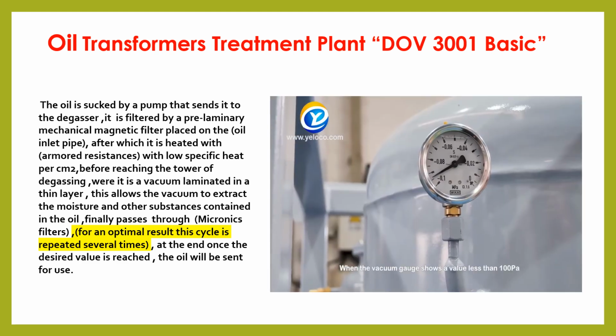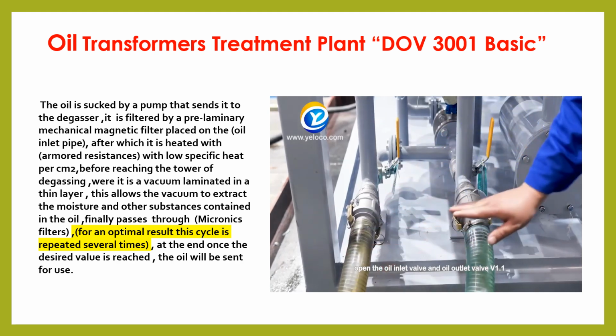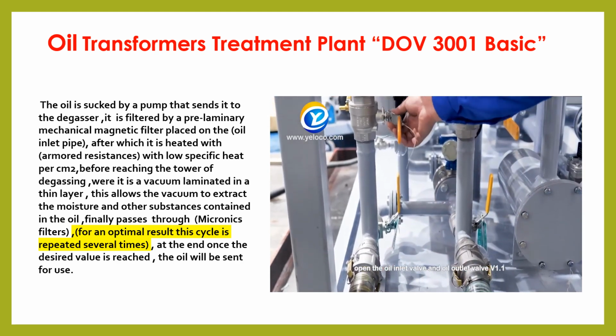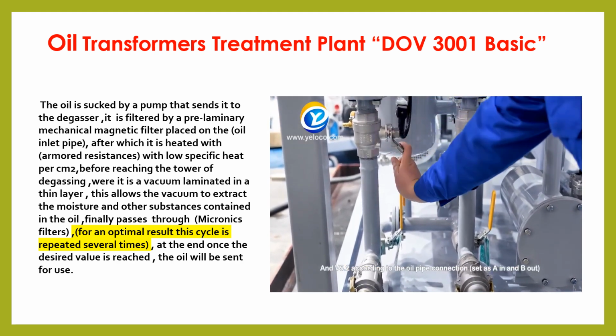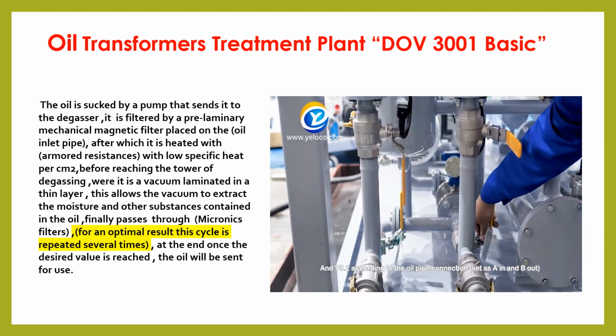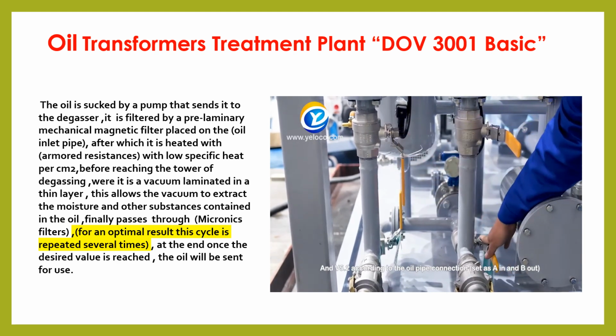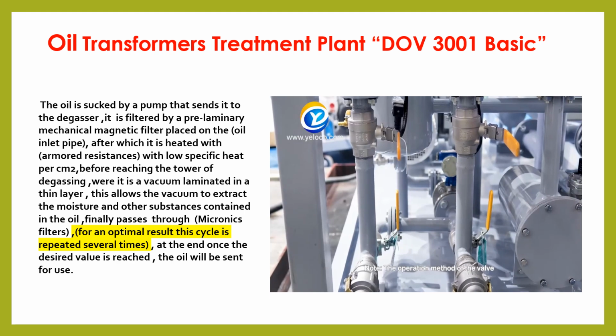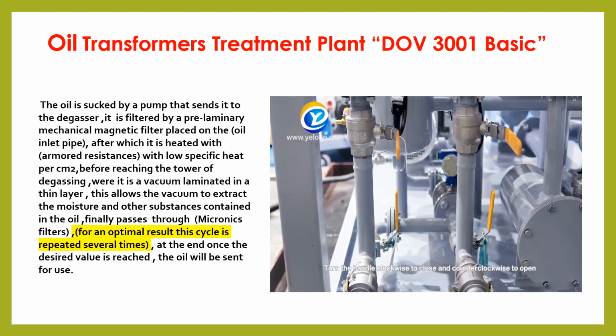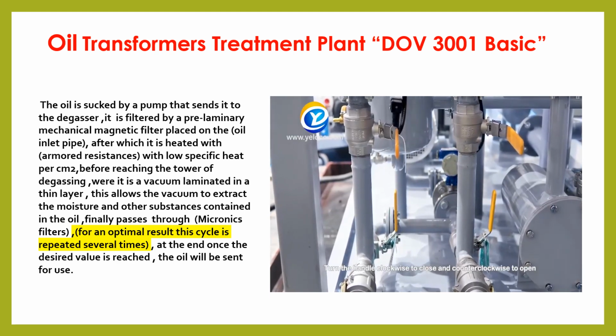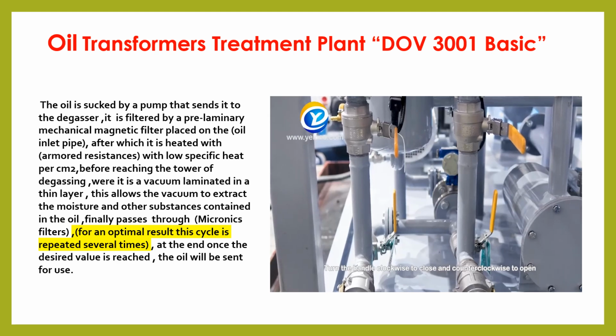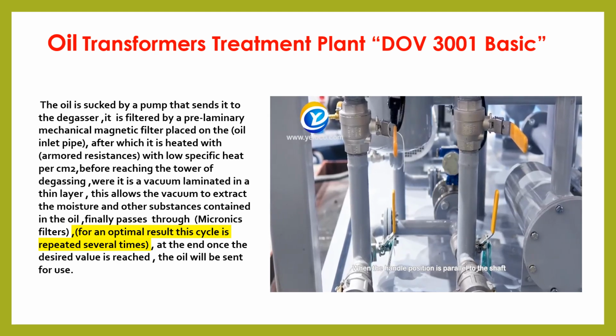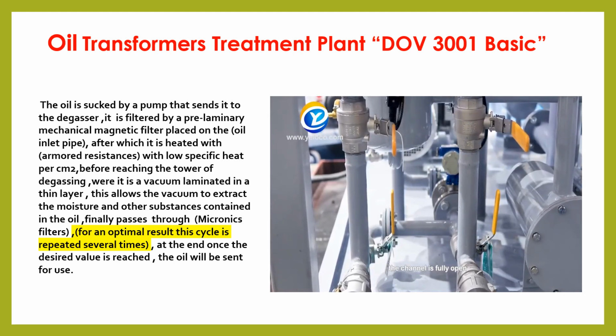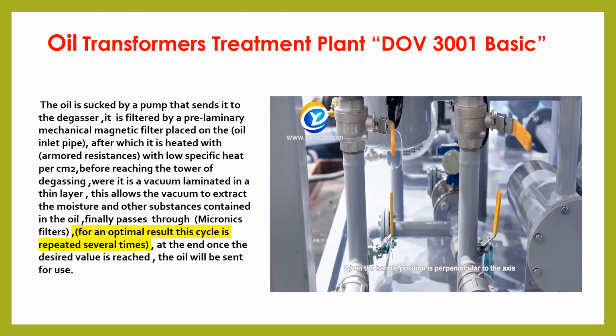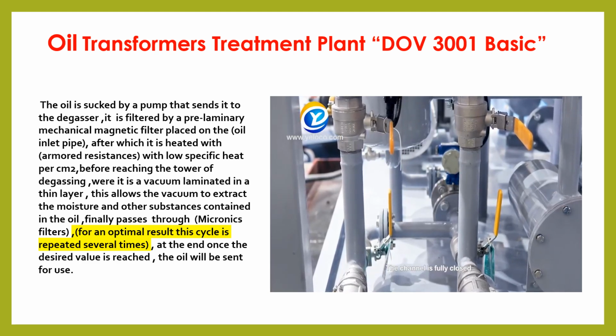When the vacuum gauge shows a value less than 100 Pa, open the oil inlet valve and oil outlet valve V1.1 and V5.2 according to the oil pipe connection, set as A in and B out. Note the operation method of the valve. Turn the handle clockwise to close and counterclockwise to open. When the handle position is parallel to the shaft, the channel is fully open. When the handle position is perpendicular to the axis, the channel is fully closed.